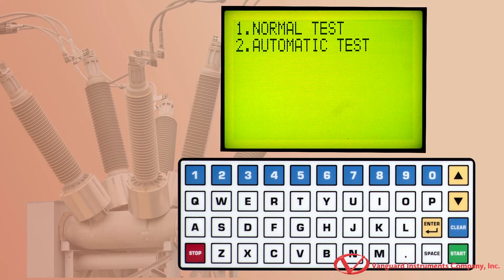From this screen you can select the testing mode. The DMOM200S3 provides a convenient automatic test mode that can be used to perform multiple tests without having to restart each test manually. When performing an automatic test, the DMOM200S3 will sense when cables are disconnected and reconnected and will initiate the test 2 seconds after sensing reconnection.